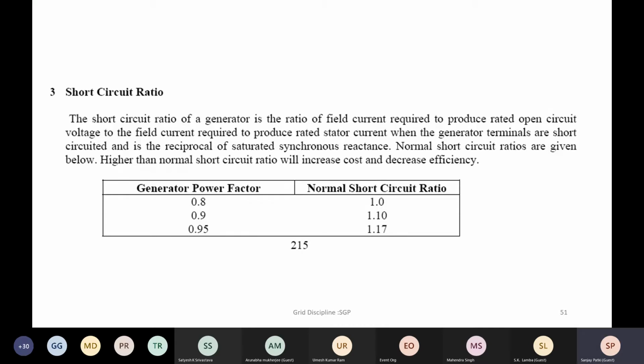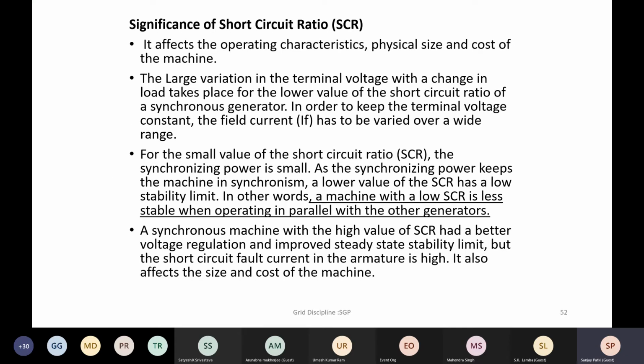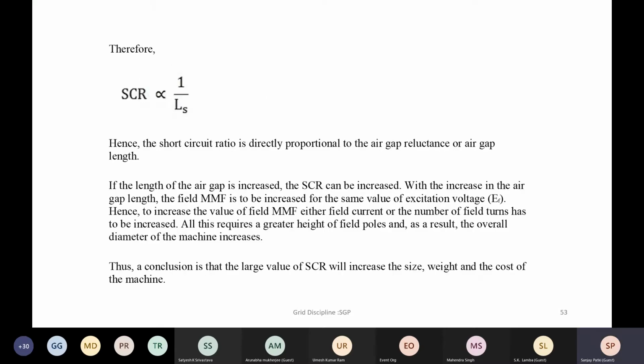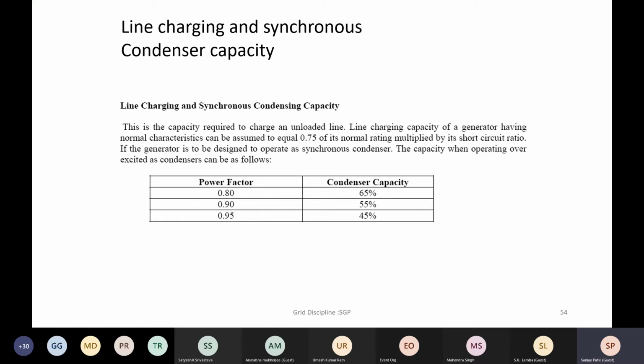So the short circuit ratio is the key parameter when you purchase a new machine, which will give you better performance. The higher the short circuit ratio, the better the performance in terms of stability, but the mass of the generator becomes bigger, so it becomes a costly machine also. So it's a techno-economic decision at a planning stage, and these are the various significances which are listed here, which you can read through in detail. So short circuit ratio becomes an important parameter as far as the capability of the machine is concerned.